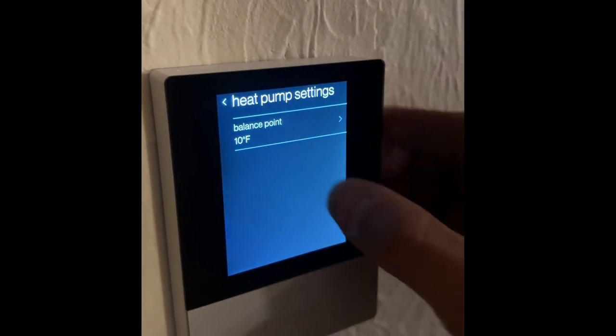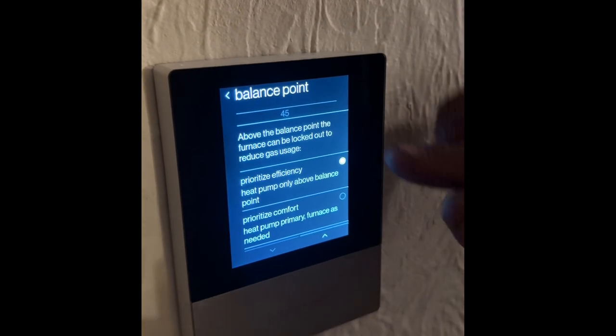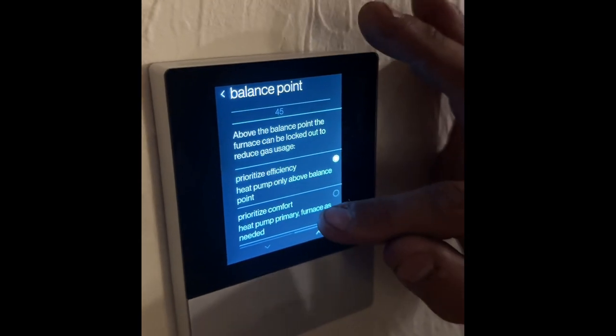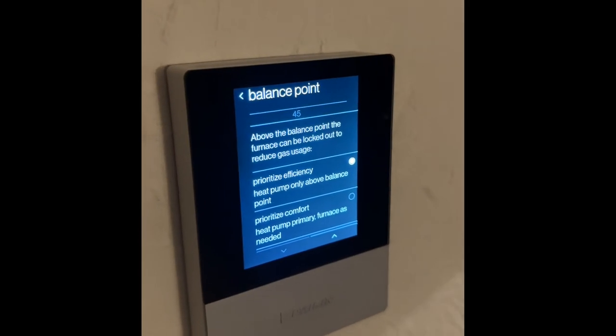Then we can select the balance point. We've changed that from 10 to 45 degrees Fahrenheit. Now you can prioritize efficiency, which means that it'll determine whether the heat pump or your supplementary heat is more efficient. Most people prefer the efficiency mode, but you could prioritize the comfort mode here too.